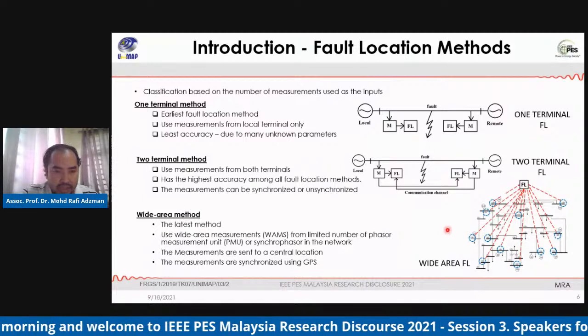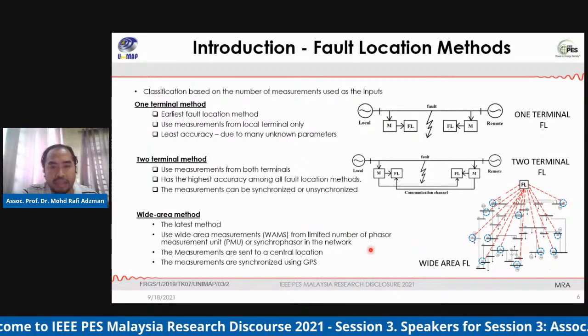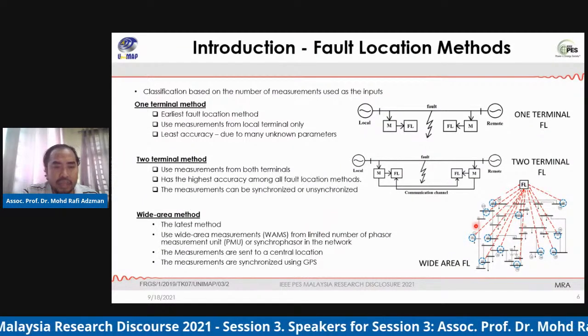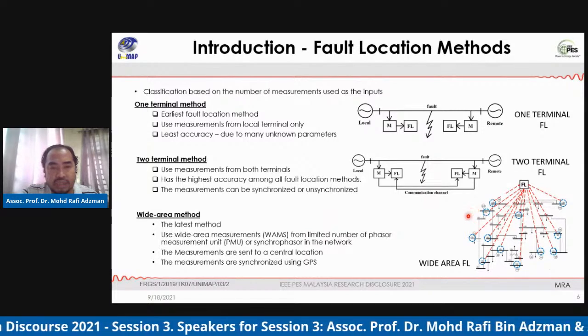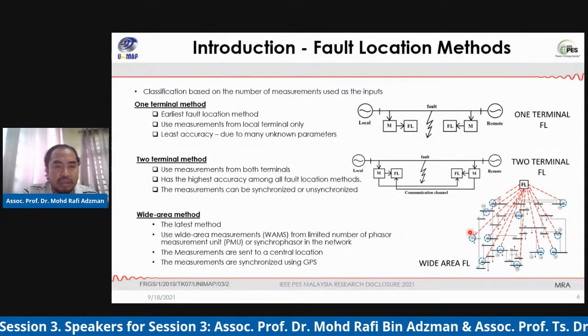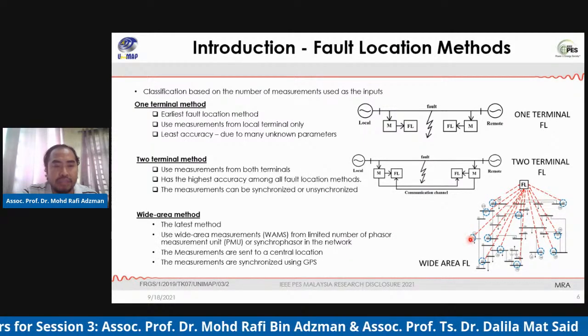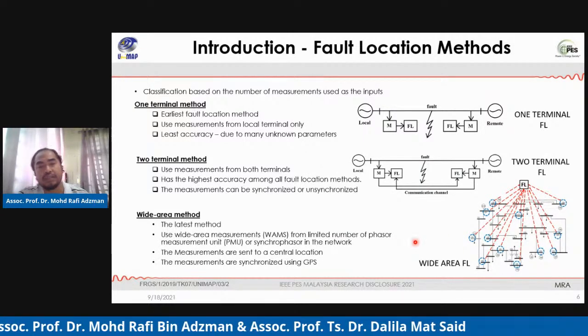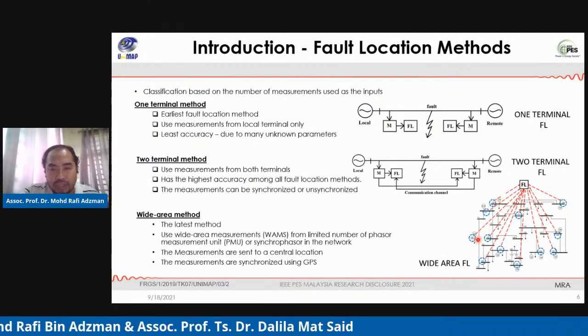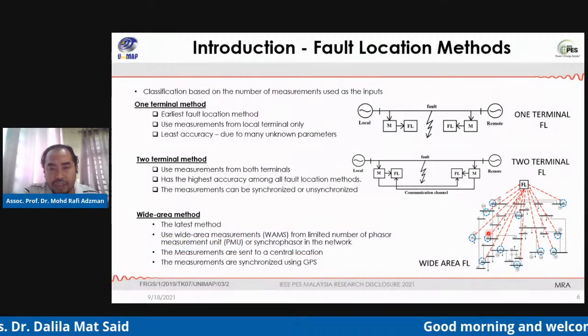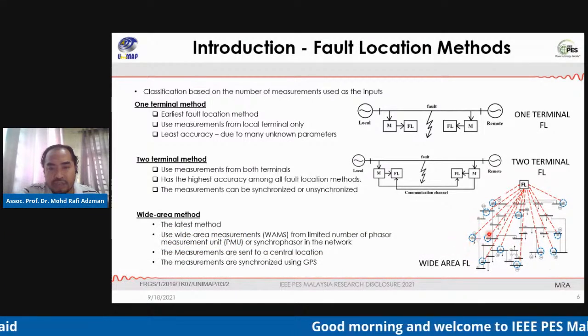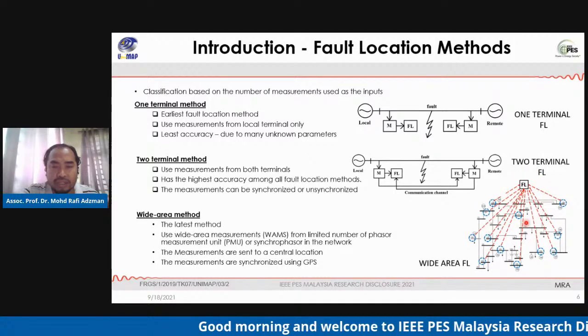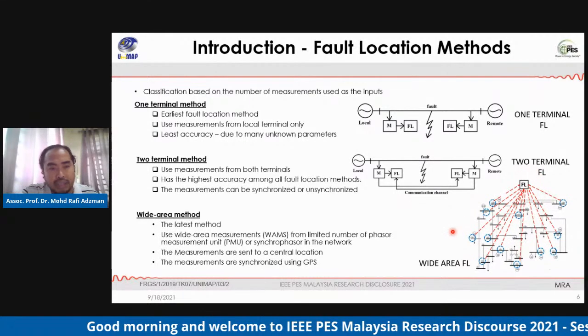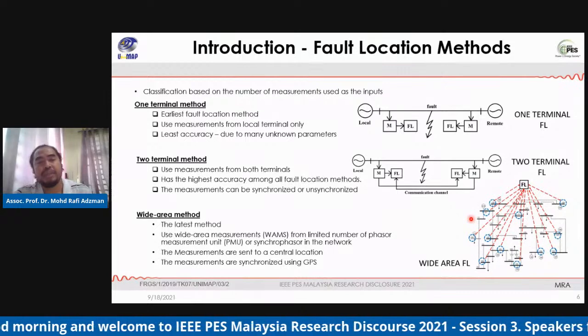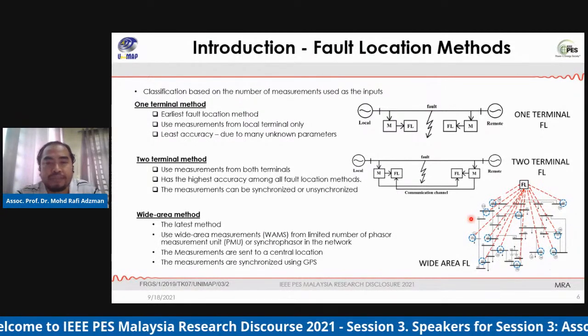And nowadays we have the latest method, known as the wide area method. So we use wide area measurements from a limited number of phasor measurement units, or PMUs, or from the synchrophasors in the network. All these PMUs or IEDs gather the information or signal and transfer it to the central location. Then the measurements can be synchronized using GPS.